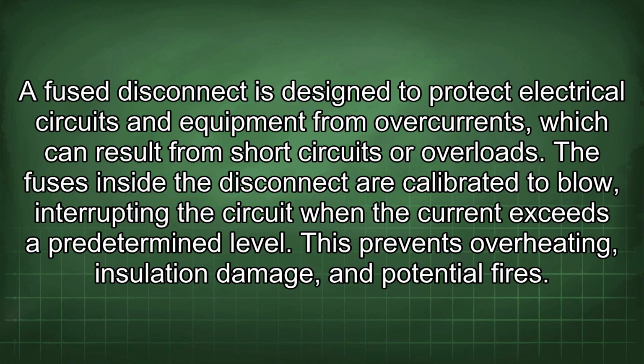A fused disconnect is designed to protect electrical circuits and equipment from overcurrent, which can result from short circuits or overloads. The fuses inside the disconnect are calibrated to blow, interrupting the circuit when the current exceeds a predetermined level. This prevents overheating, insulation damage, and potential fires.